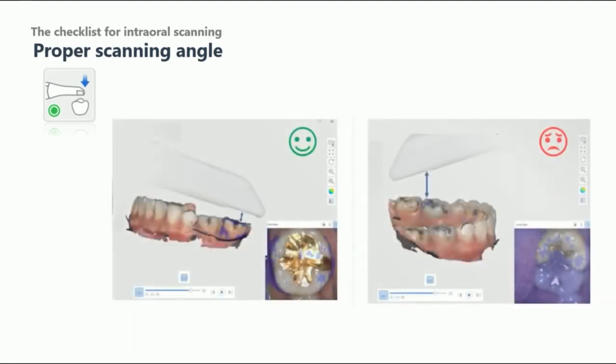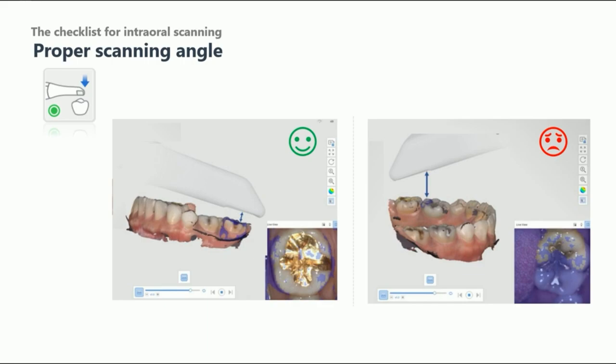Lastly, please keep the proper distance between the scanner and the teeth. If the tip is too close or too far to the teeth, the scanner may stop and you'll see purple masking on the live view screen.